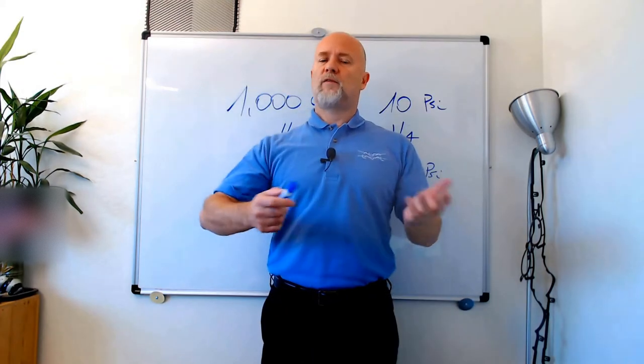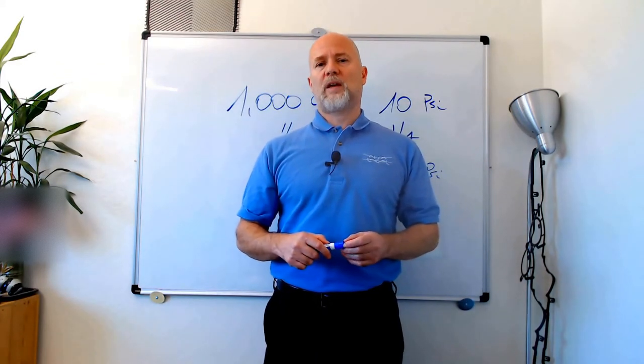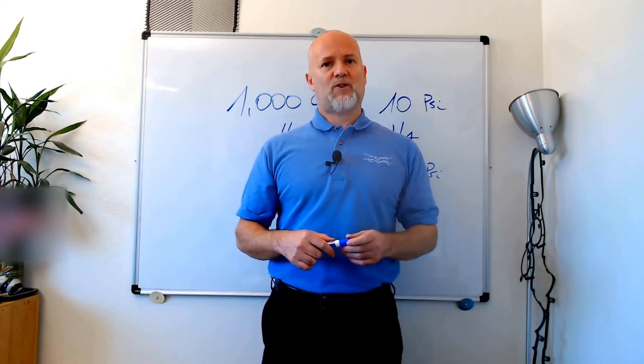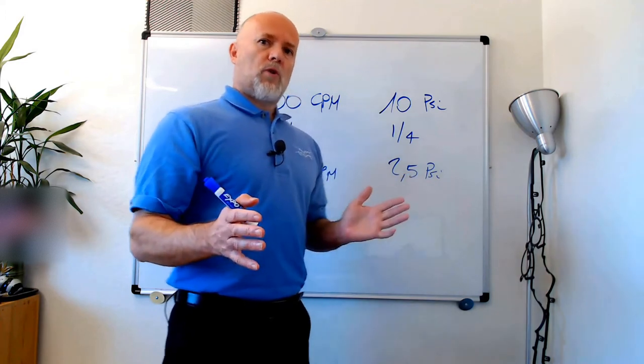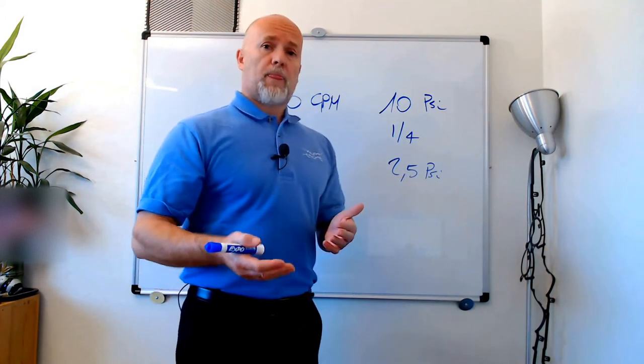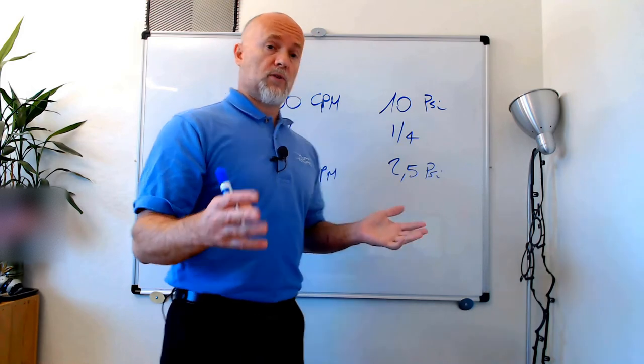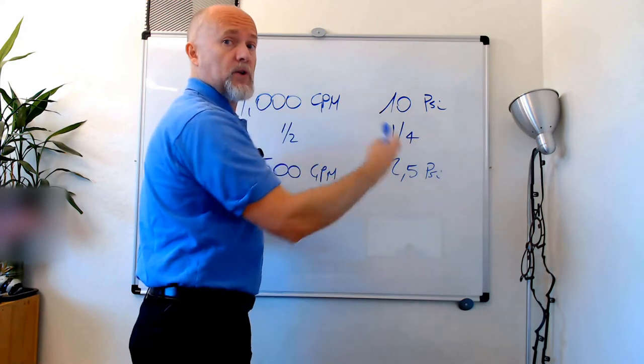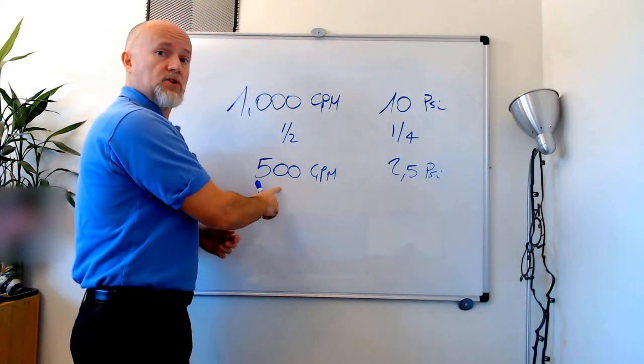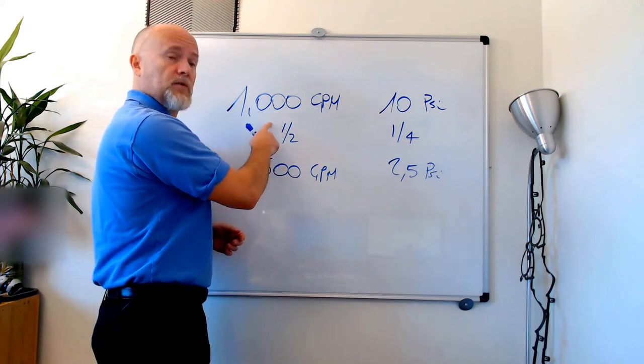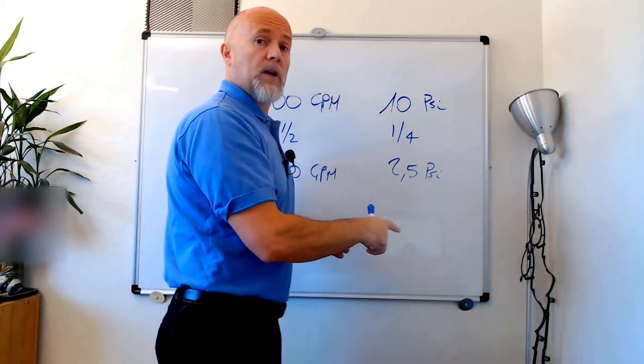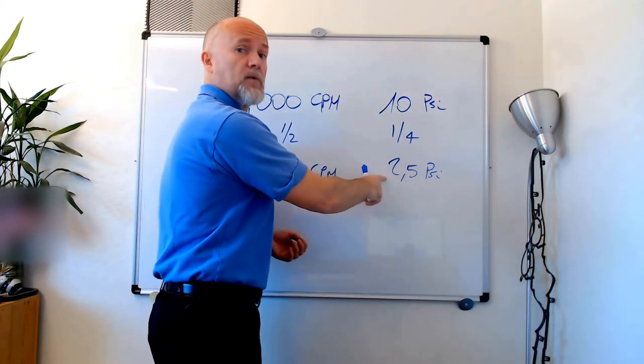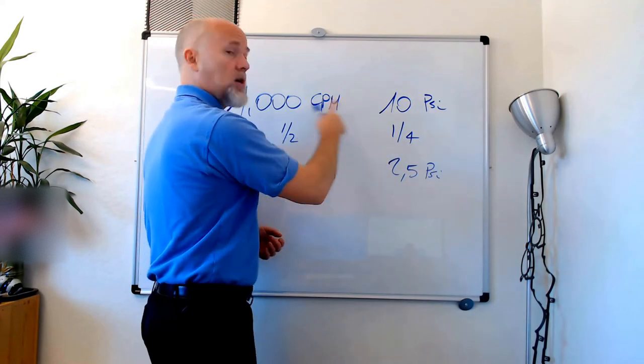It would be impossible to make a video about pressure drop without talking about shear stress and the consequence of partial load in a heat exchanger. You have to remember that the pressure drop decreases with the square of the decrease of the throughput. So if you design a heat exchanger for 1,000 gallons per minute with 10 psi pressure drop design, but then you run the heat exchanger at 500 gallons per minute (half of the design throughput), the pressure drop is not going to be 5 psi (half), but it's going to be 2.5 psi because it's one quarter, the square of the difference.